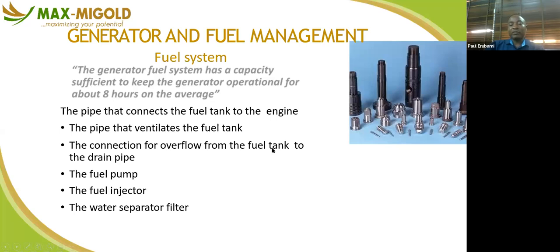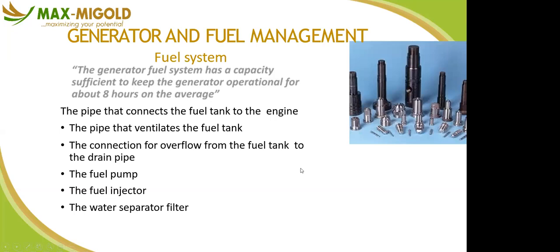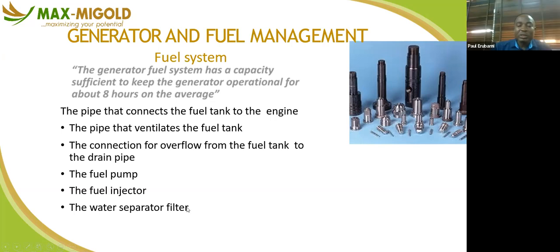So for you to have adequate or free flow of fuel into your generator, you ensure that the water separator is always clean. There is no sludge or clogged element around the water separator, because if there is, it will resist the flow of fuel to your generator. That's why your generator will not be able to carry the desired load. So it starts tripping, and you say there's something wrong with the generator.